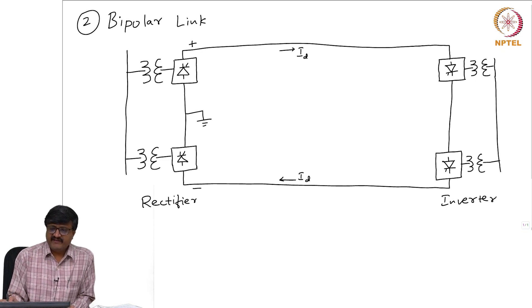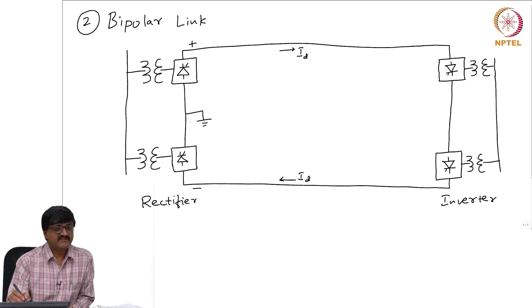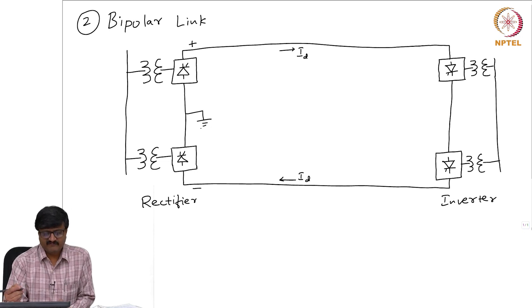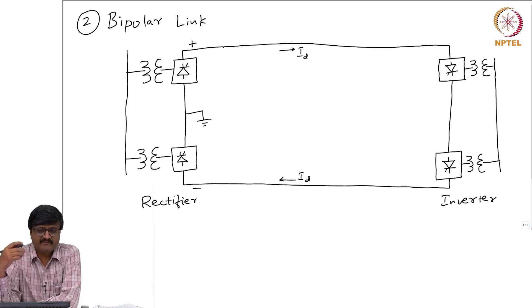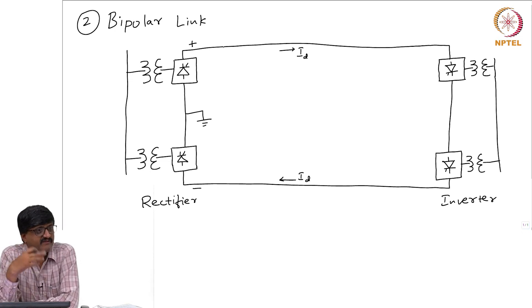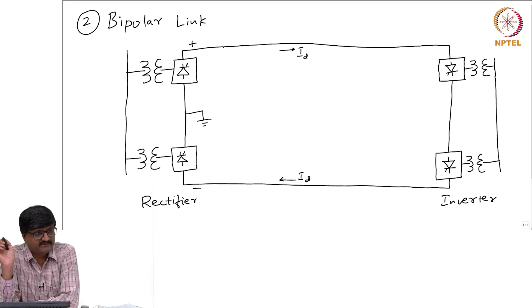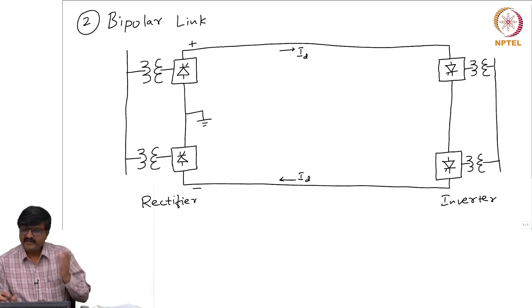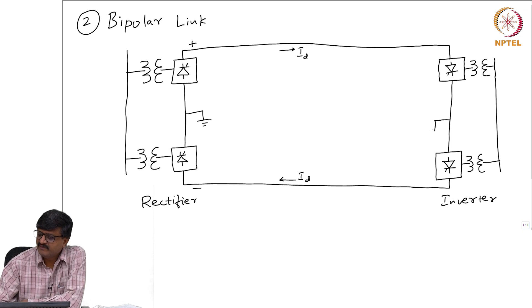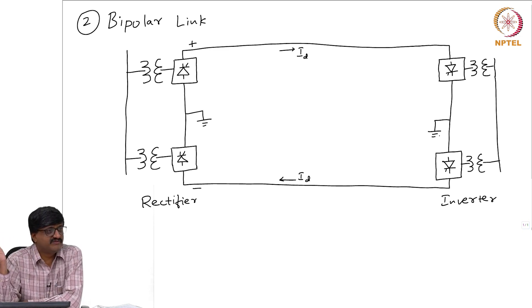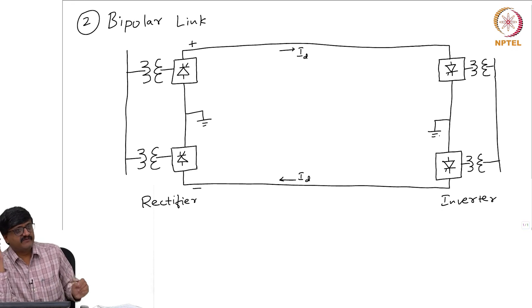At each side we have two 12-pulse converters and there is a midpoint on the DC side which is grounded. Please note we need grounding so that the two conductors are at the same magnitude of potential with respect to ground — one is positive, the other is negative — but the magnitude of the voltage between any conductor and ground is the same. Sometimes grounding is provided at both sides, though on rare occasions; even one side will do, but at least one side has to be grounded.